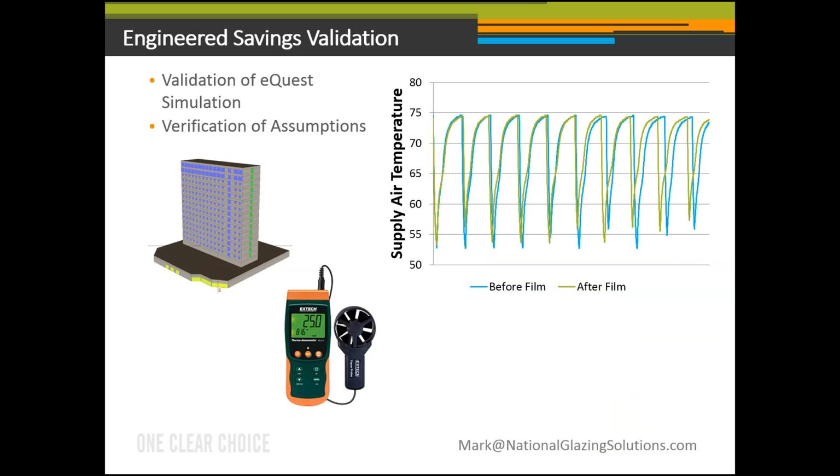You all know, or likely know, the IPMVP protocols occur over a very long period of time, the duration, and compare data to data. The ESV, on the other hand, compares data to simulation. It's similar to option D, except that the scope of an ESV is a smaller representation of the building shell than M and V, and the period of evaluation for ESV is typically a month or less.